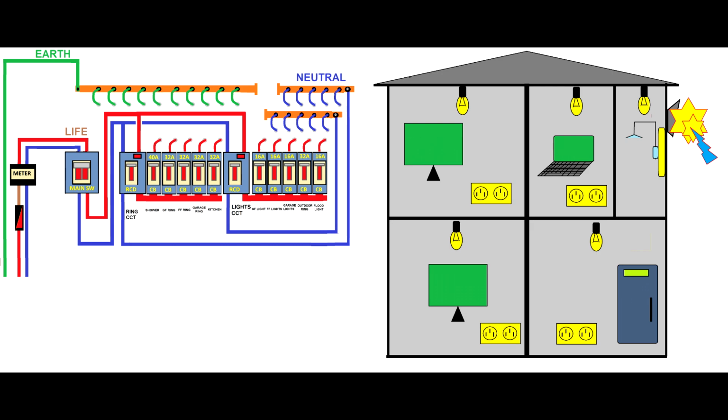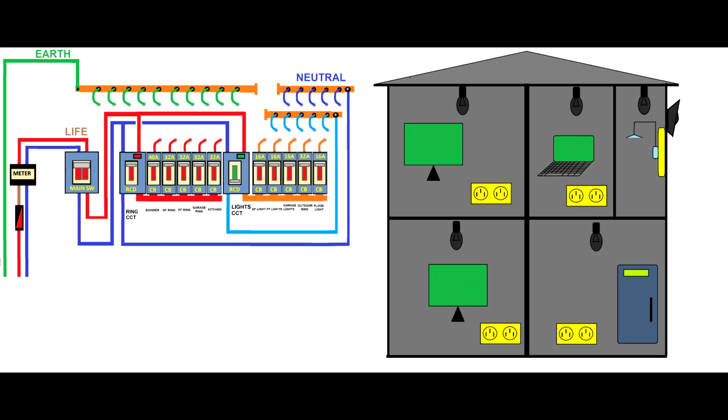So if you look at the right hand side on top, the floodlight, because of the moisture outside, starts to have an earth leak. If we used one RCD, the entire home would be not only in darkness, but you'd also lose the sockets and your fridge. In this case, the RCD which protects the light circuits tripped because I have an earth leak.